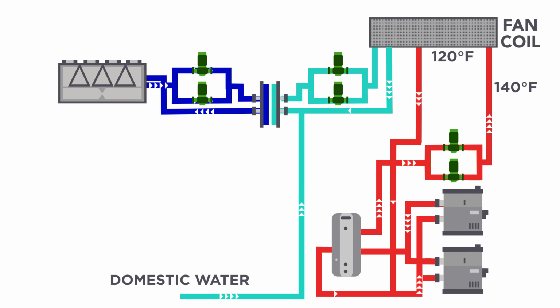Since a chiller is not potable water rated, a plate exchanger is used to isolate it from the water itself. When the thermostat calls for cooling, a two-way valve opens on our designated cooling coil and mechanically chilled 50-degree domestic cold water runs through the coil to provide cooling for the space. Once the water has passed through the coil and cooled the space, it is returned into the return pipe we added to the cold water piping system, and it is sent back past the chiller to be recooled if required.